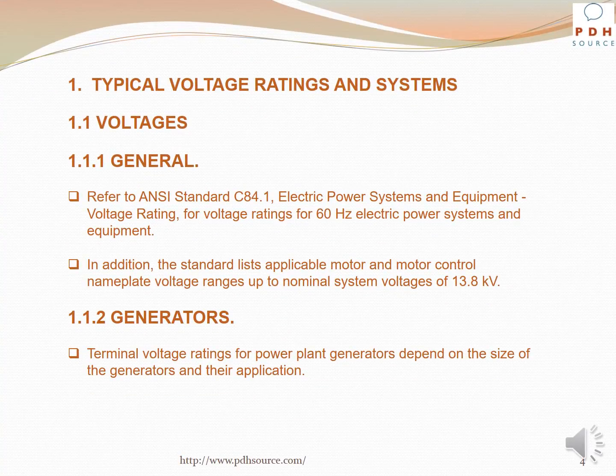Typical voltage ratings and systems refer to ANSI standard C84.1, electric power systems and equipment voltage ratings for 60 Hertz electric power systems and equipment. In addition, the standard lists applicable motor and motor control nameplate voltage ranges up to nominal system voltages of 13.8 kV. Terminal voltage ratings for power plant generators depend on the size of the generators and their application.